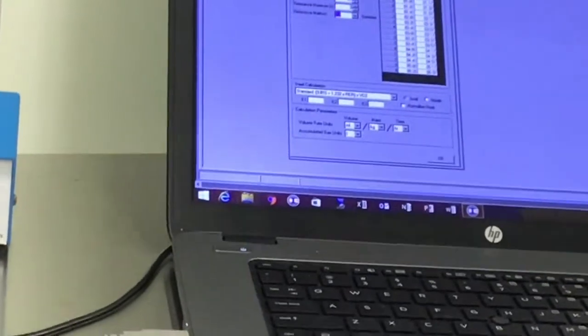There's another one, cage settle. To understand cage settle, I have to explain a little thing here. We're going from cage 1 to cage 2, switching from cage 1 to cage 2. How do we make sure that the air in cage 1 is not mixed with the sample in cage 2? When we measure cage 1, before measuring cage 2, we are purging for 17 seconds. We are sucking from cage 2, but we are not measuring for 17 seconds. 17 seconds is what will guarantee that cage 1 sample didn't corrupt cage 2.